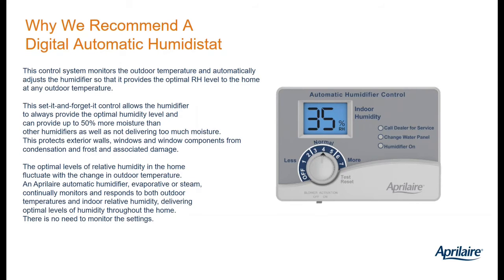It's a huge advantage. If you think about a manual humidistat, now the consumer, the occupant of the home, is the one that has to know what the outside temperature is, and they're the one that has to go adjust the manual humidistat. But we know they're not going to do that. Maybe, if we're lucky, they do it once per day. Usually what happens is they see damaging condensation on the windows, so they lower the humidistat, but they never raise it back up. So they're not getting as much of a benefit as they could be. So really consider the advantage to the consumer of the automatic humidistat.